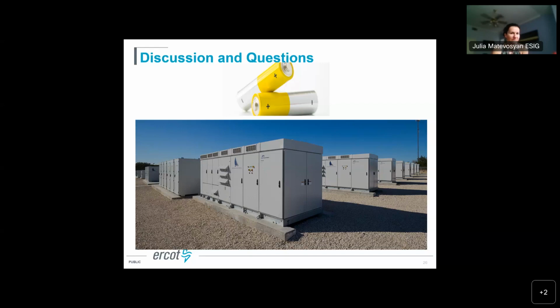So our real-time market sends a base point instruction of where it wants the battery to operate at in the next 5 minutes. So that base point instruction is sent every 5 minutes. Regulation deployment occurs on a 4-second basis, and they may dispatch the battery up or down based off of where frequency is at that given point in time.